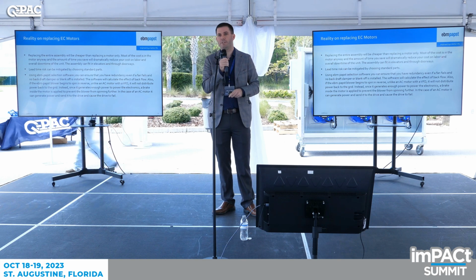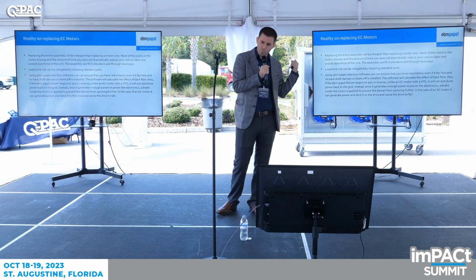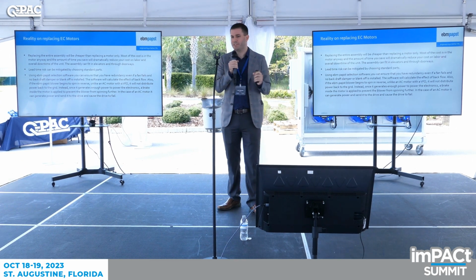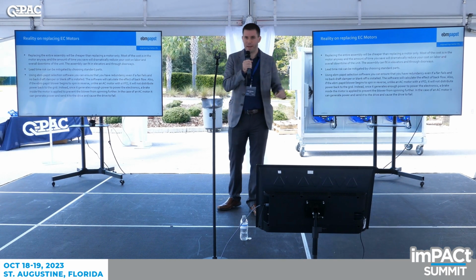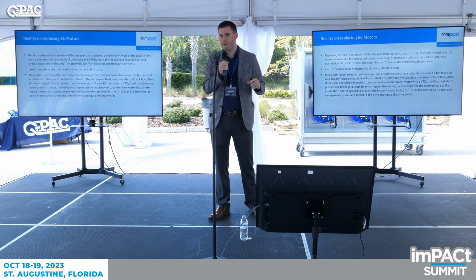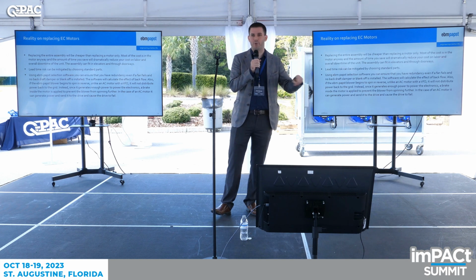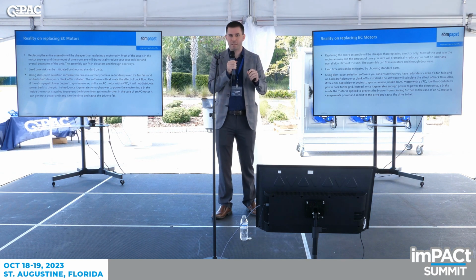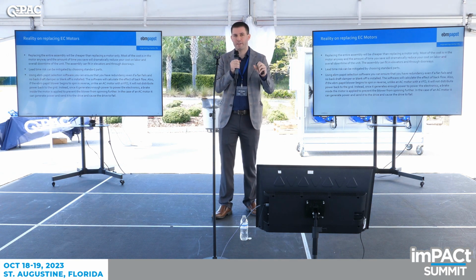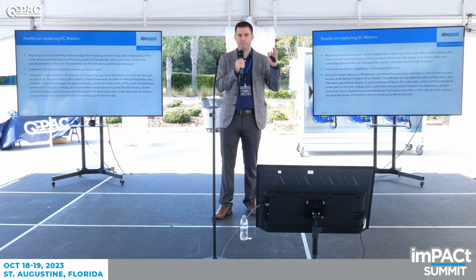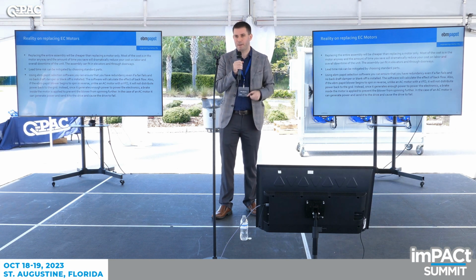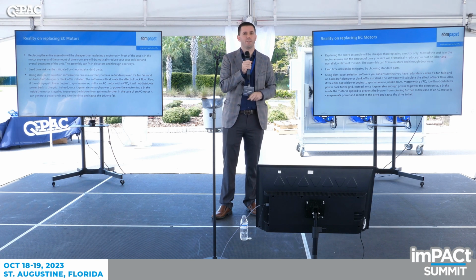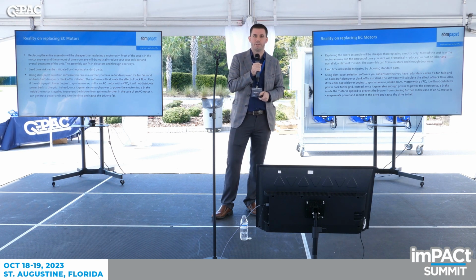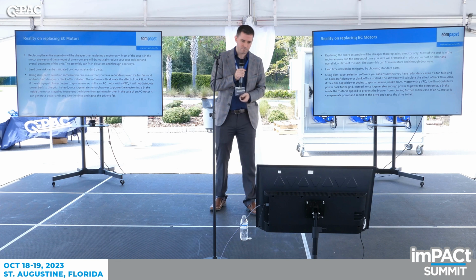You're actually preventing that recirculation, preventing that generation. With our EC fan, when it fails, it still spins backwards and still generates power, but it is smart enough to power its own electronics, realize it's spinning backwards, and then there's an electronic brake inside of it, and it dissipates all the energy by applying that brake to the fan, and it'll just keep doing that. So it never actually allows the energy to escape the fan itself.